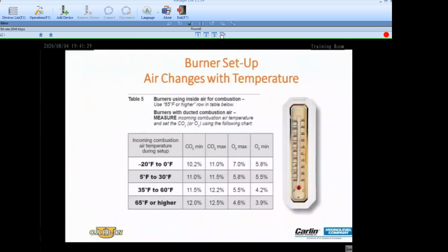When we talk about taking in combustion air from the outside, there are guidelines for setting up the burner for the coldest air possible. On the coldest day in that region, when that burner is drawing the cooler air, your air saturation will be greater, your oxygen level will be greater. If it's not set to a table like this, there's a good possibility you're going to over-air the appliance, and you may have some rough starts. So it's important that we follow guidelines on minimum and maximum CO2 levels based on outside temperature.